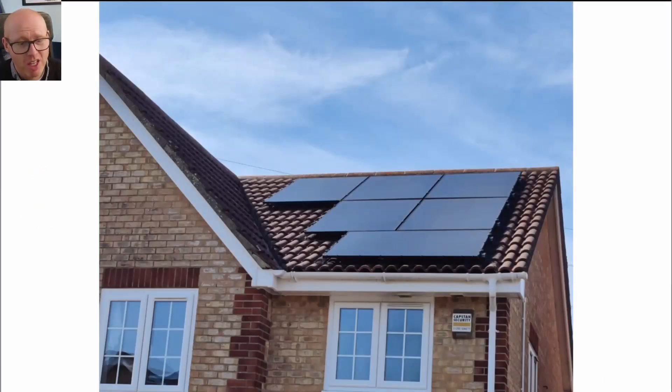This image from last month at about 3 p.m. shows that the hard shading line — the sun is just too high in the sky — we just don't get the hard shading we thought we were going to get. In the winter months the optimizers may perform more of a function, and depending on your surroundings, trees and other factors, optimizers may be more useful to you than they are for me. I do like the per-panel monitoring though — the data geek in me enjoys that.